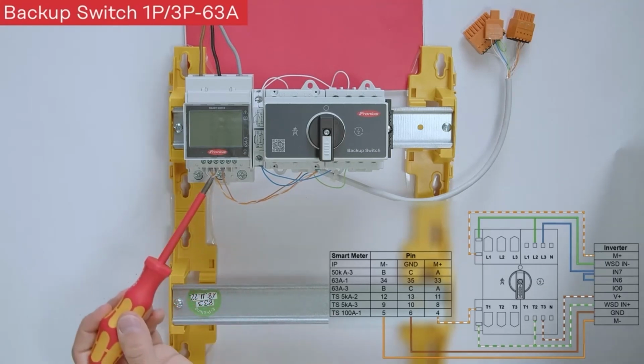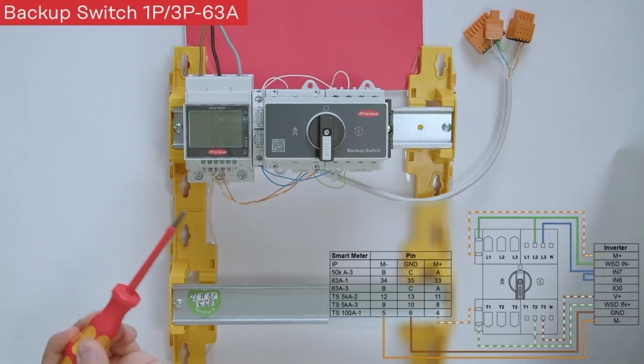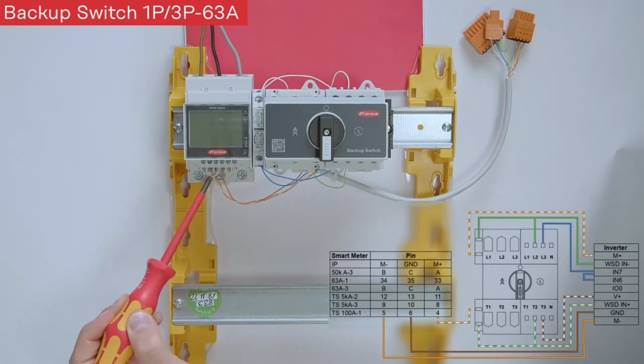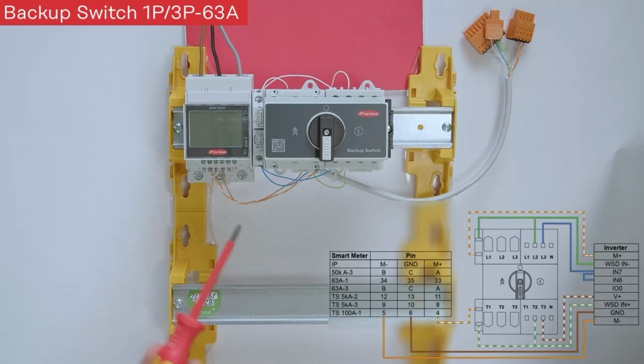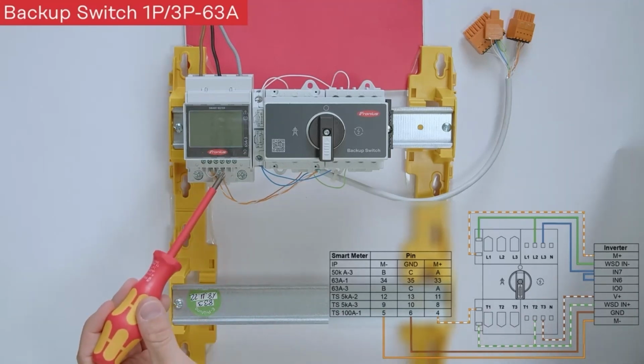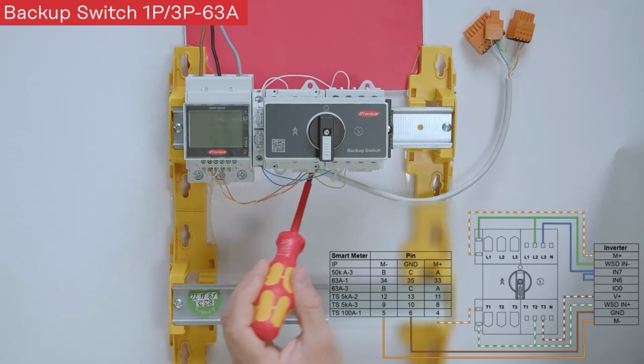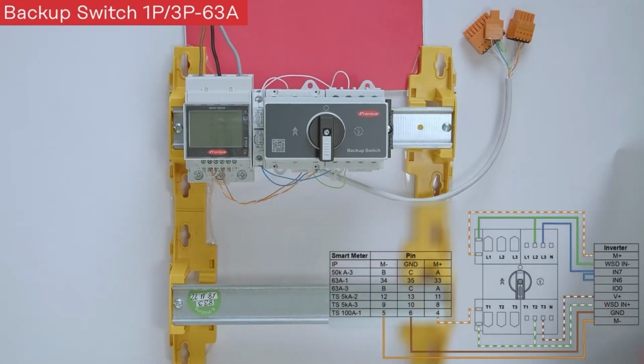So that means that we have here the data plus, data minus and ground connection, as well as a termination resistance of 120 ohm to terminate the Modbus line on one side. So from there we go from the Fronius smart meter on to the Fronius inverter, and furthermore we need a data communication also on the backup switch to make sure that the backup power mode is active and stays active.